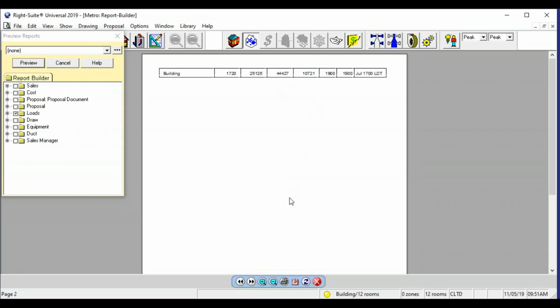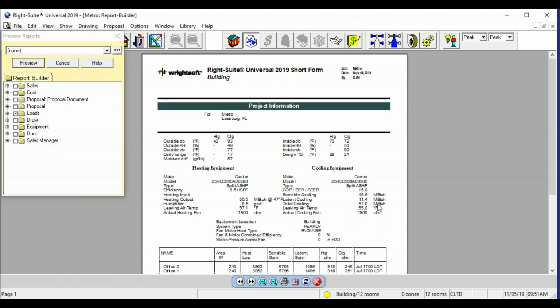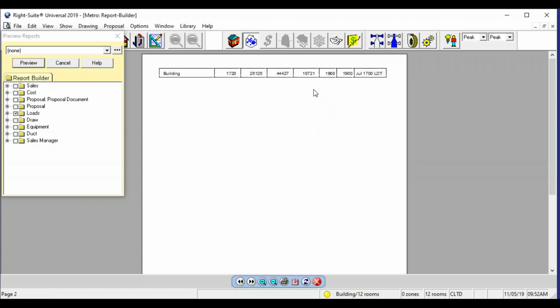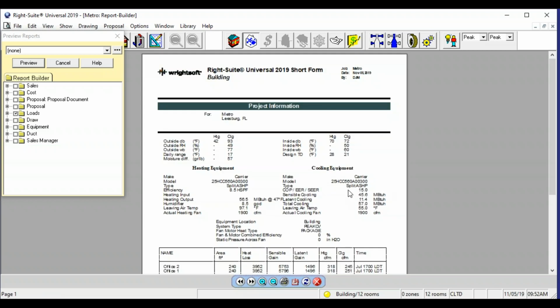So our sensible load is going to be 44,427, and our sensible capability is 45,600. And we have a latent of 11.4. Now remember, I changed my SHR, the sensible heat ratio, to 0.8. We can change it back to a 0.7. Typically, it ranges between a 0.7 and a 0.8, and there's several variables that are factors in that. But at the end of the day, when you're doing your design, half of whatever your remaining latent can be converted back over into sensible. So if we did it as a 0.7, then you can take your remaining latent, put it back over to your sensible, and as long as you fall within those parameters, you're fine.